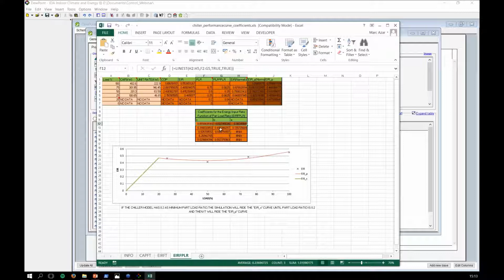What it allows you to do is say, from no load to my chiller to 100% load, so that's the part load ratio, what is the cooling capacity? This is some data you would get from the manufacturer. And what is the electricity consumption of that chiller? If you input these light brownish data cells, it automatically generates these coefficients A, B, and C, and you can input those directly. So you can go ahead and use this Excel to get a more realistic performance curve of the COP.